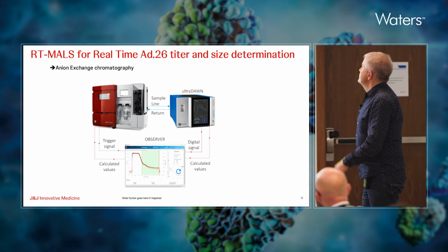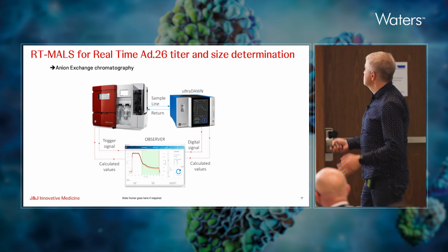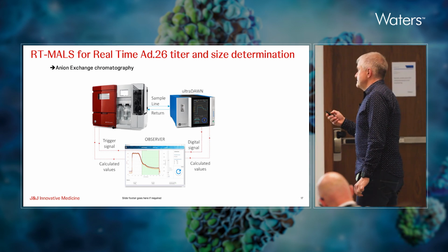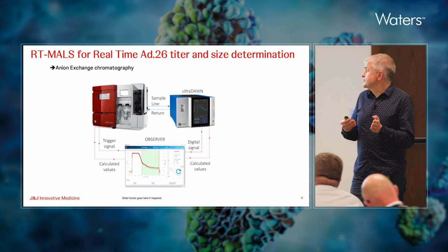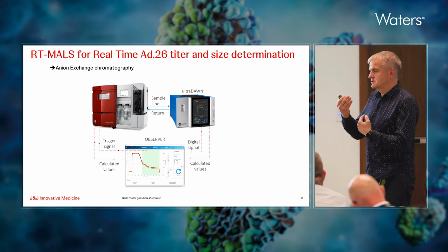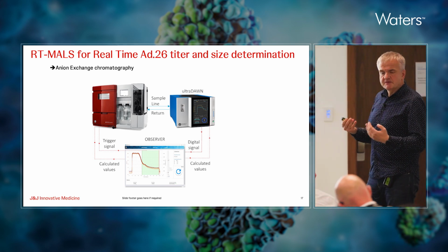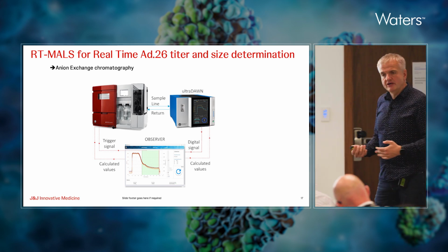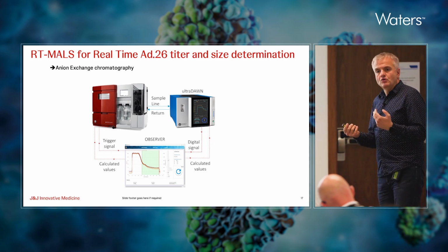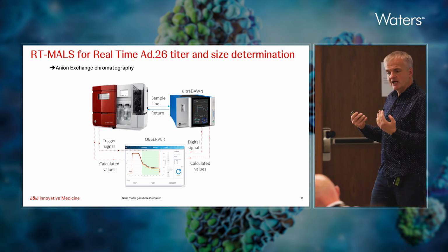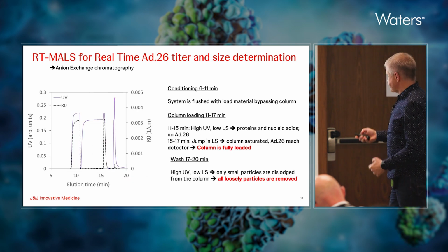In the first experiment, we coupled the Ultra-Dawn to purification systems, just an ÄKTA, via the Observer software. The Observer software is able to trigger signals and calculate values, so it's kind of a feedback system that helps, especially in production, to start, stop, but also select what you want to see, what you don't want to see, what you want to collect, what you don't want to collect, based on the properties of the material.